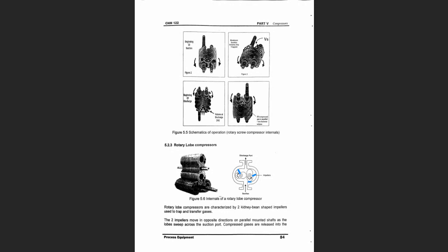I have a very small clearance. فيه عندي فراغ بسيط جدا ما بين the loop, okay, and the casing of the pump. And we have already discussed why this clearance should be minimized as much as possible. Why? Because when we compress a liquid or when we pump a liquid or a gas, the pressure here will be higher than the pressure here.